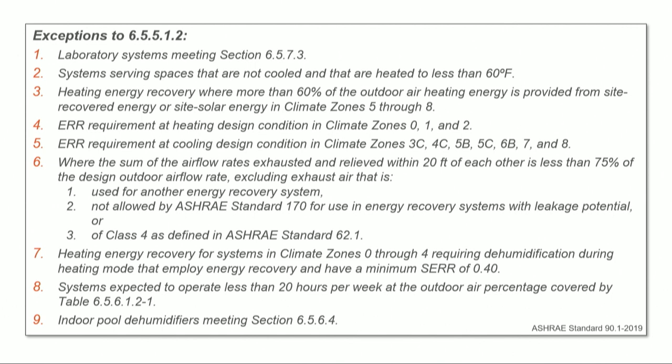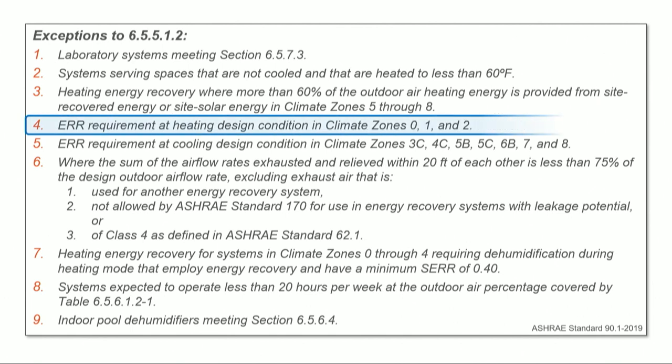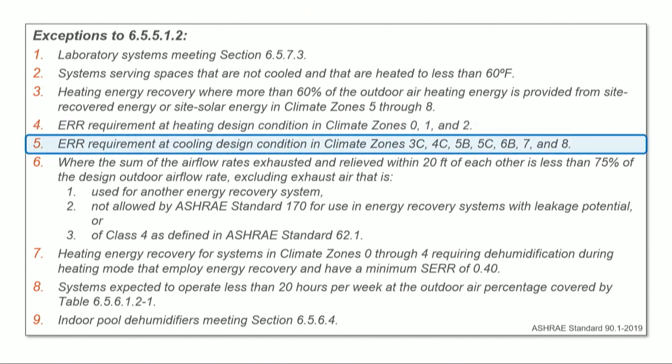Here is a list of exceptions for this section. Exceptions 4 and 5 address climate-specific conditions: in the warmest climate zone, the energy recovery system does not need to meet the 50% enthalpy recovery ratio at heating design conditions, only at cooling design. In colder and drier climates, the 50% ratio need only be met at heating design conditions, not at cooling design. A good reference for the other exceptions is the Standard 90.1 user's manual, which ASHRAE publishes to accompany the standard.